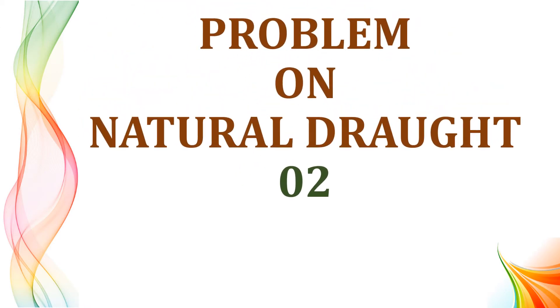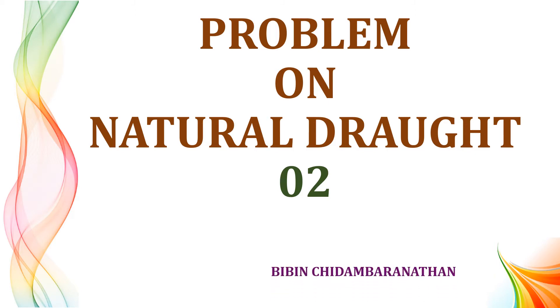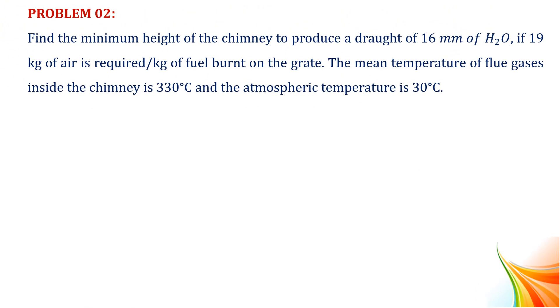Welcome to this session on solving problems on natural draught. Problem 2: Find the minimum height of the chimney to produce a draught of 16 mm of water, if 19 kg of air is required per kg of fuel burned on the grate. The mean temperature of the flue gases inside the chimney is 330 degrees centigrade and the atmospheric temperature is 30 degrees centigrade.